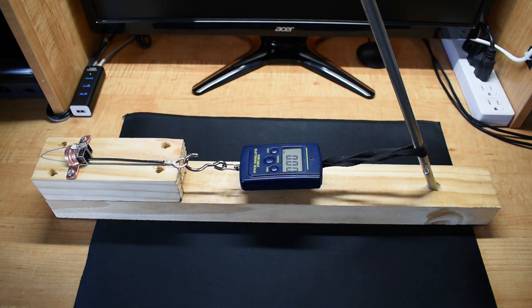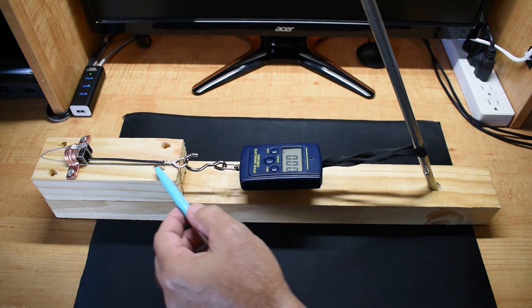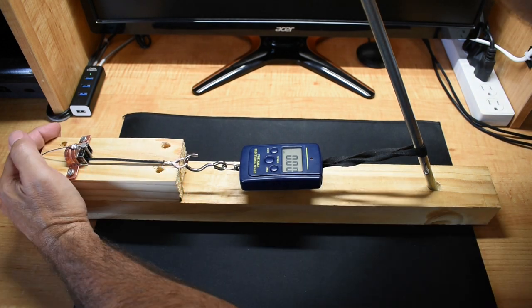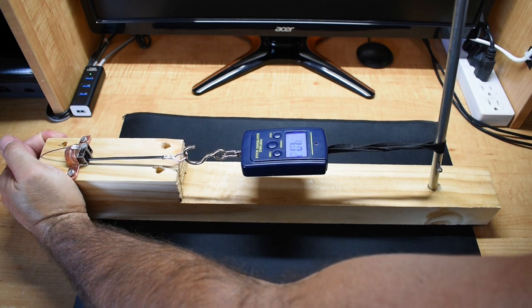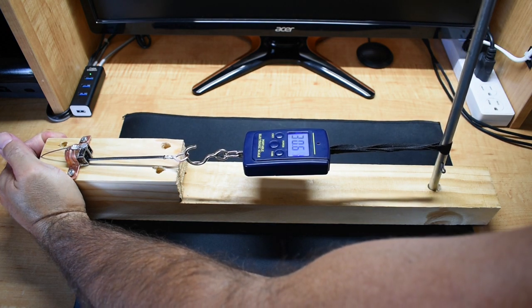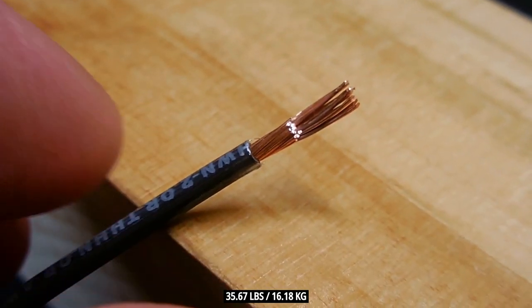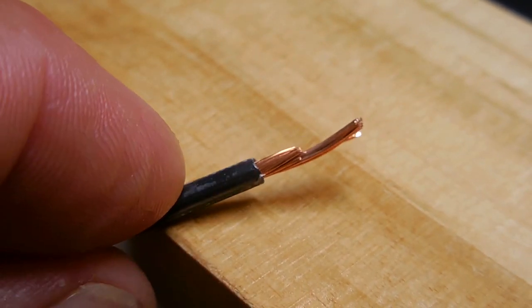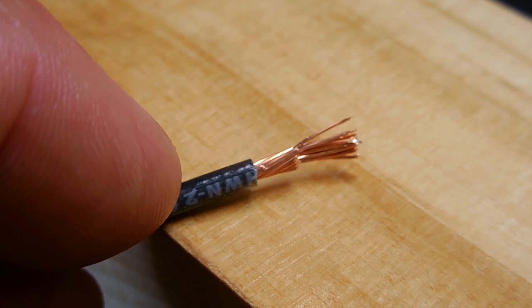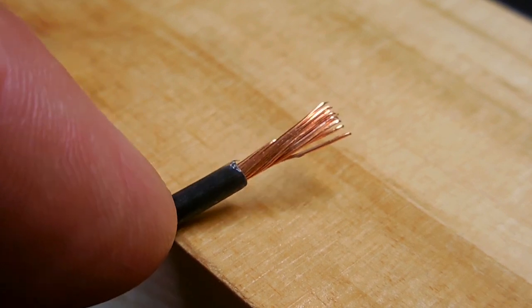Now we're going to be testing the lower port of the Wago 773 stranded wire. And looking at the stranded wire that was pulled from the 773 connector you can see many of the individual strands were sheared off.